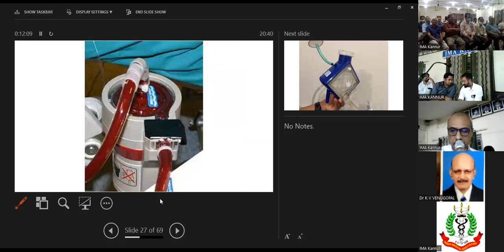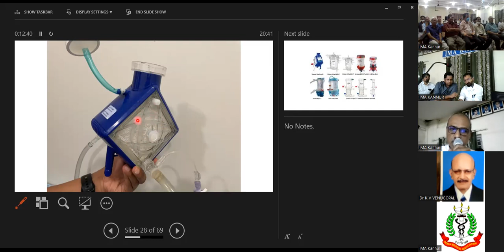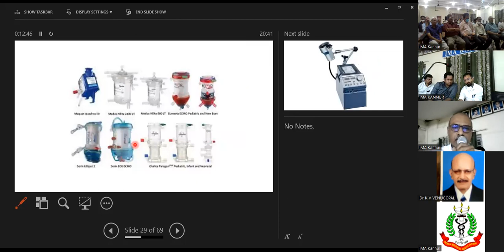This is one of our oxygenators. As I said, inside here you have a large number of microtubules through which blood flows. Inside the tube is the oxygen, the air delivery, whatever gas you're using. Usually it's a mixture of compressed air and oxygen. How much oxygen percentage depends on the patient's condition. And outside those tubings, when it's in use, the rest of the oxygenator is filled with blood. Different companies have different configurations. You have adult and pediatric and neonatal, all different.